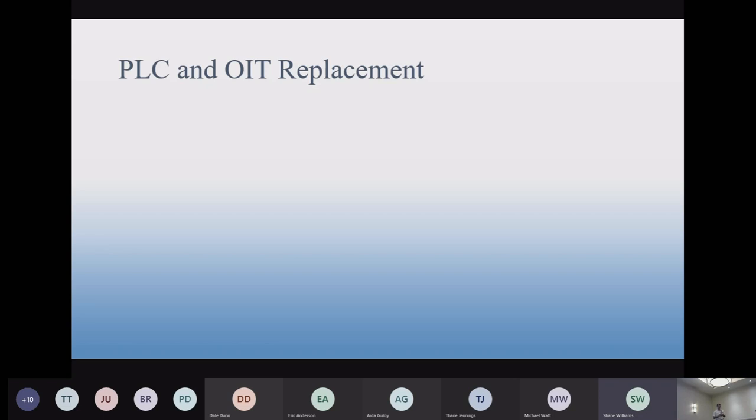But a lot of times the installer of the line, the contractor, puts it up, and it's 3 feet above the probe. They think it's great to have extra. So now you either can move that line and zigzag it, or you want to do the whole line over again. Or you just cut that 3 feet off.